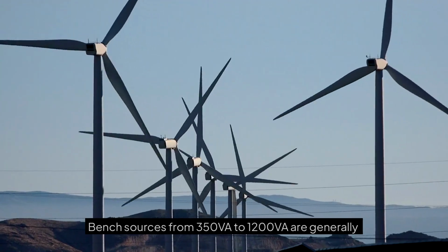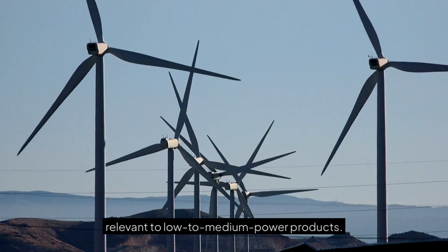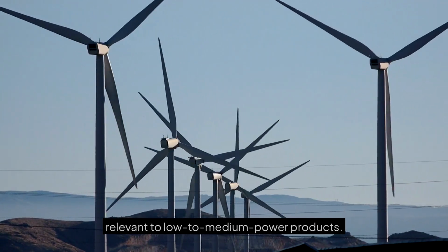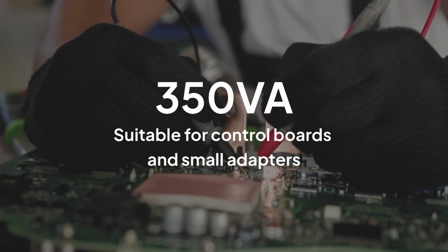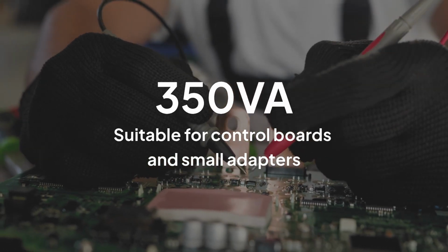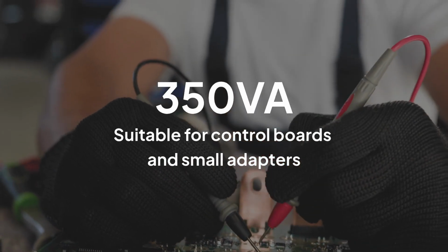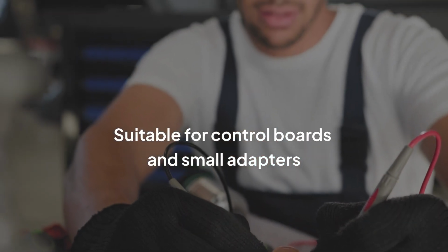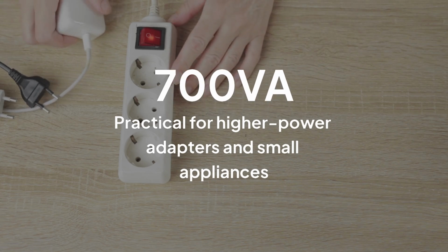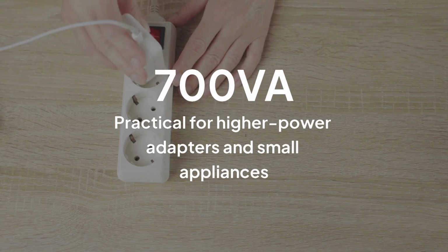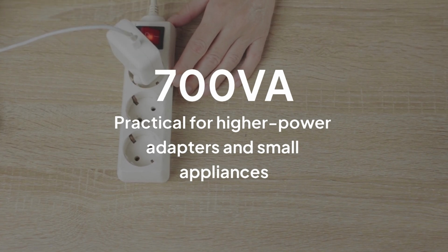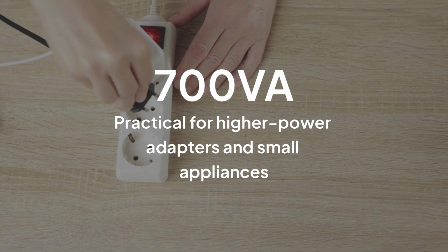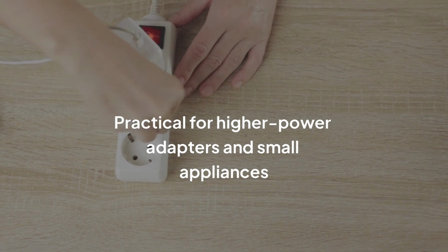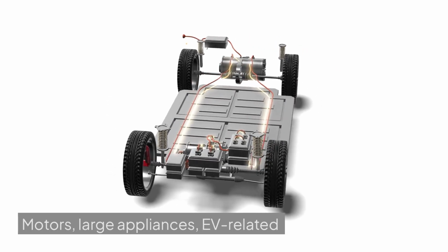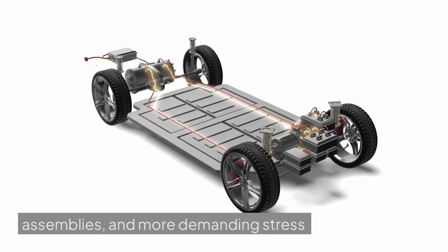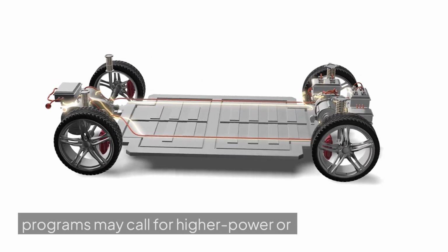Bench sources from 350 VA to 1200 VA are generally relevant to low to medium power products. A 350 VA unit may suit control boards, small adapters, instruments, education benches, and service diagnostics when startup demand is modest. Ratings of 700 VA or 1200 VA become more practical for higher power adapters, multiple devices, small appliances, or prototypes with uncertain inrush. Motors, large appliances, EV-related assemblies, and more demanding stress programs may call for higher power or regenerative systems.